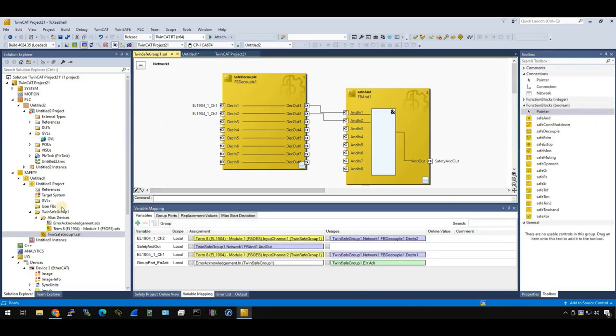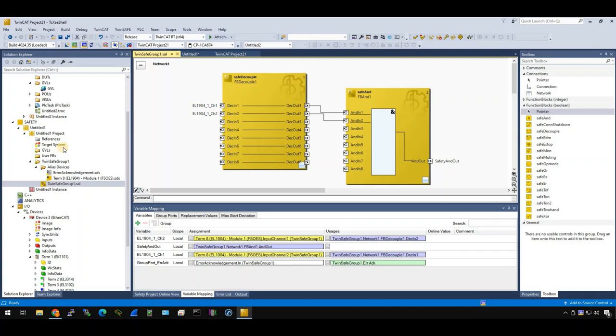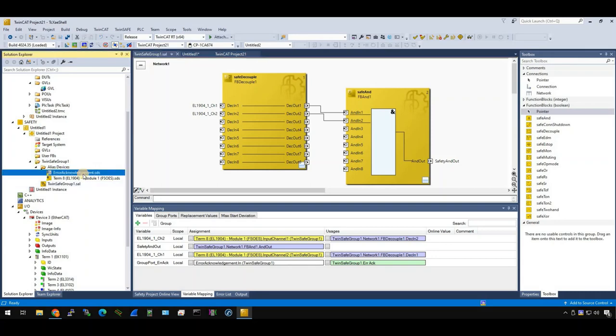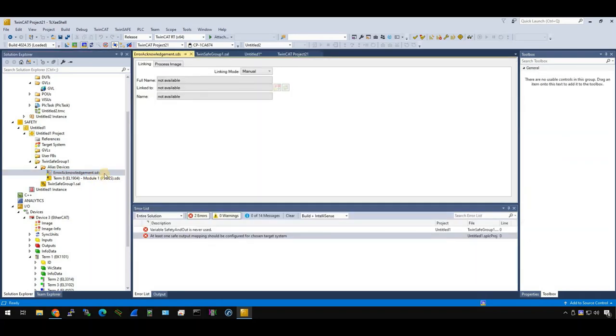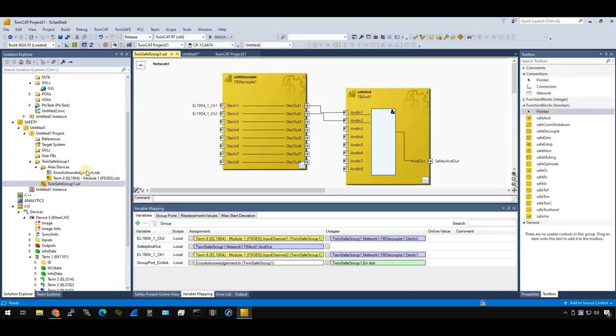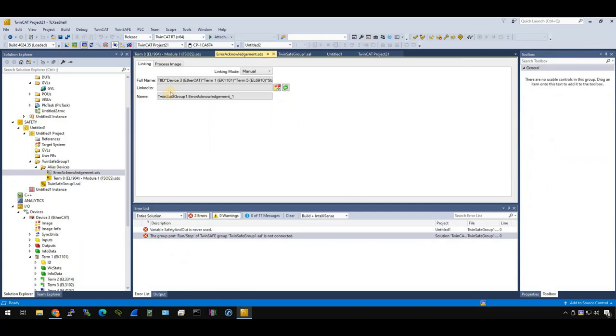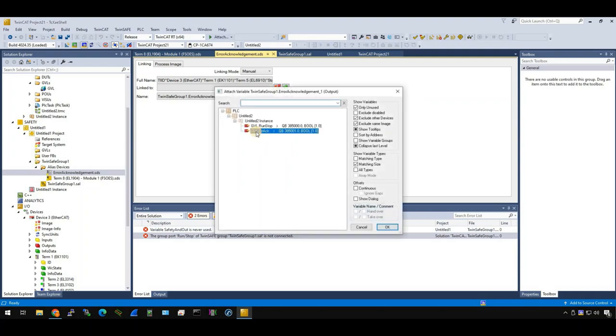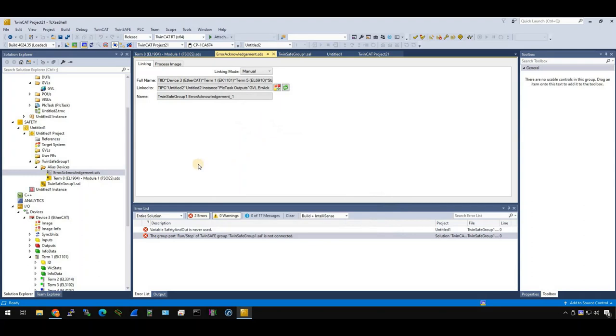And go back to our TwinSafe project. Before we do it, let's link the error acknowledgement first. Do you remember that we create a safety project with pre-configuration error acknowledgement? The error acknowledgement is this SDS. You can trigger it to reset the group error. Okay, so how can we link it? Just see here is a link, link to, view here, press the plus button to choose this error_ack, finish. Very easy.